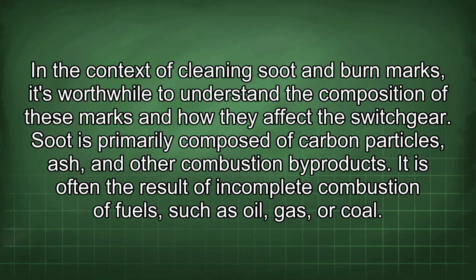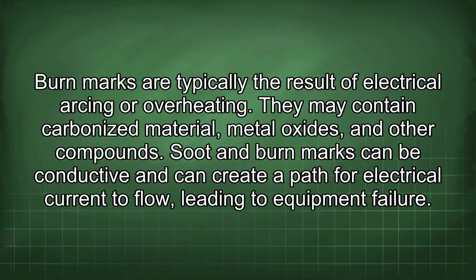In the context of cleaning soot and burn marks, it's worthwhile to understand the composition of these marks and how they affect the switchgear. Soot is primarily composed of carbon particles, ash, and other combustion byproducts. It is often the result of incomplete combustion of fuels, such as oil, gas, or coal. Burn marks are typically the result of electrical arcing or overheating. They may contain carbonized material, metal oxides, and other compounds.